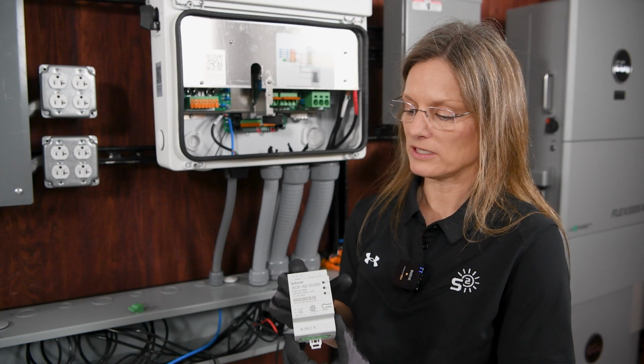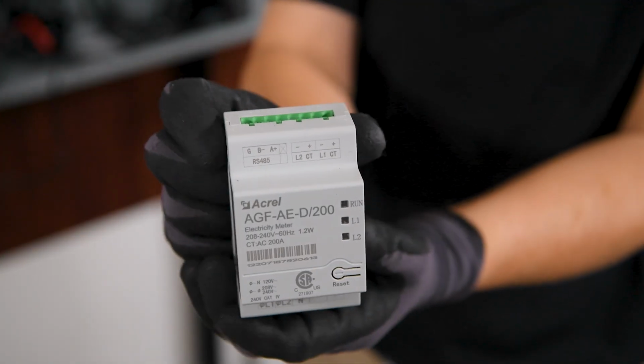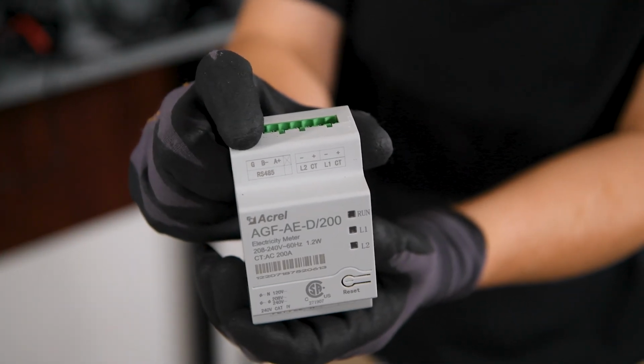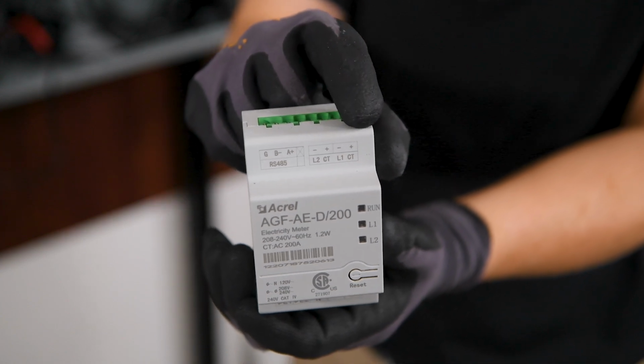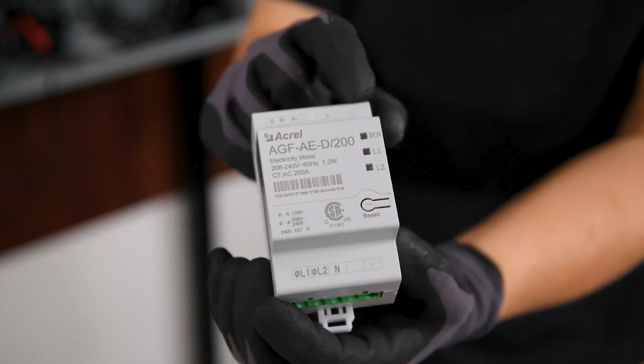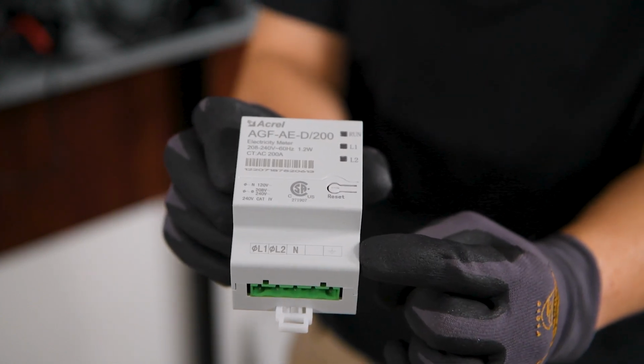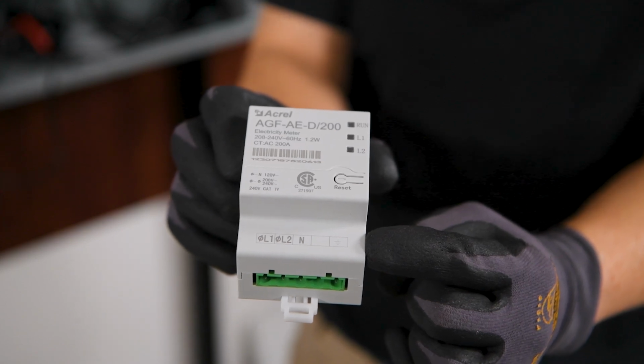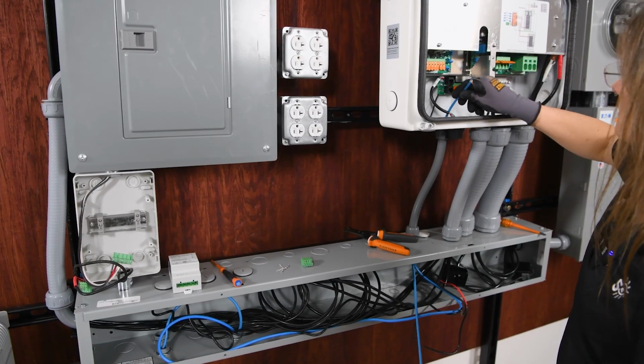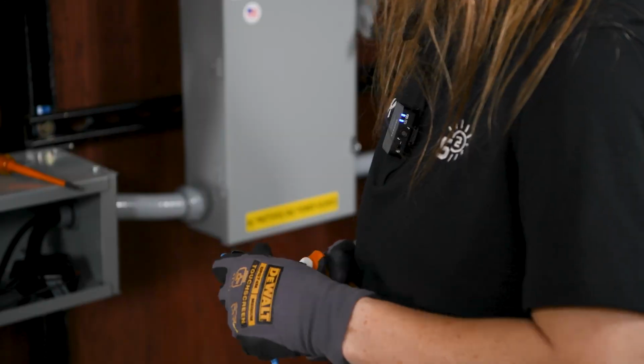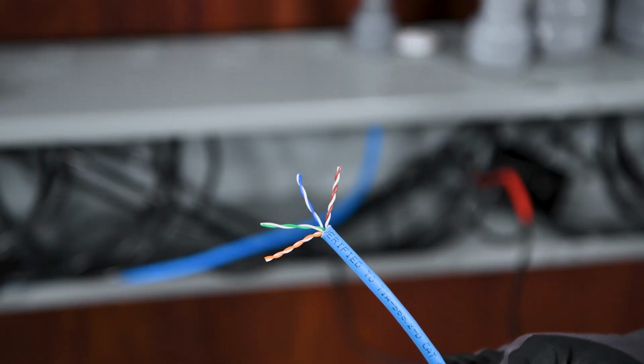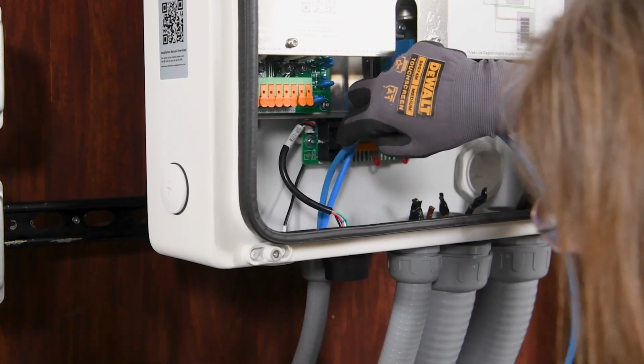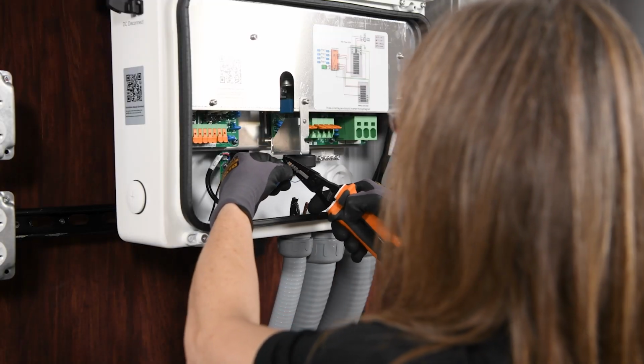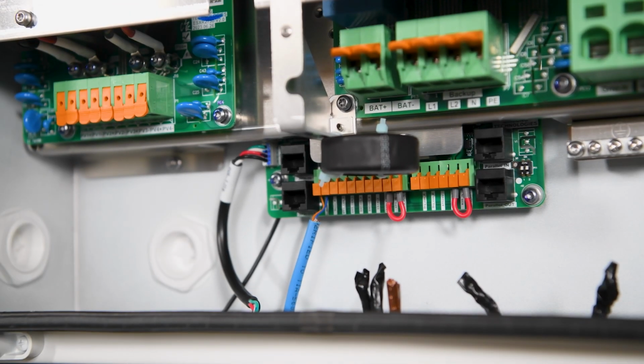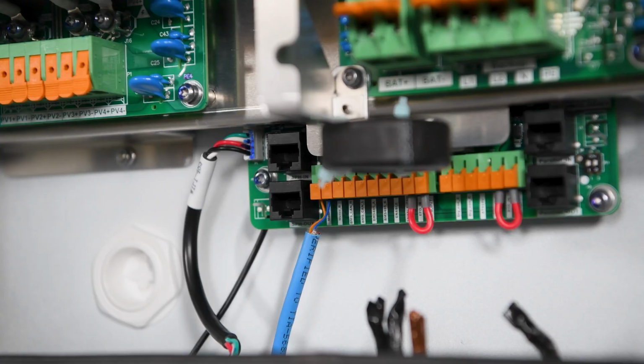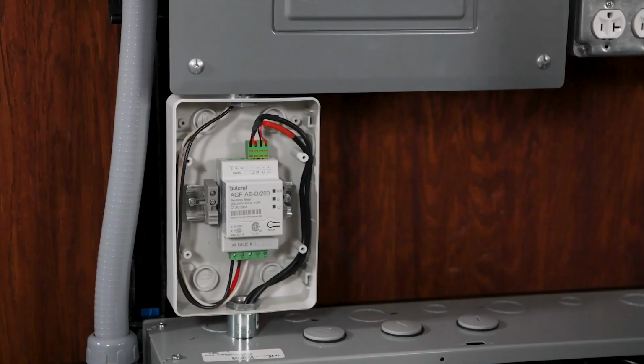They have 3 different inputs. On the top left of your meter, this will be your communications with the inverter. On the top right, this will measure the current from your CTs that you will install. And on the bottom left, it will read voltage. So we are using a standard Cat5 cable or RS485 cable, and it doesn't matter which of these cables you choose to use, as long as whichever color cable you use in A on the communications board inside the inverter, you use the same color in your Acrel meter.